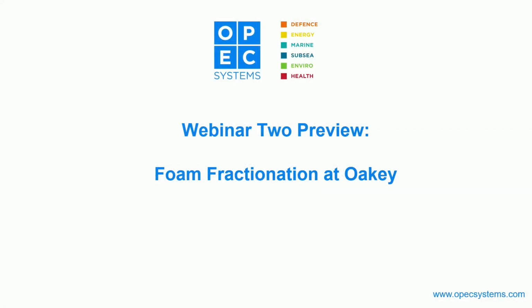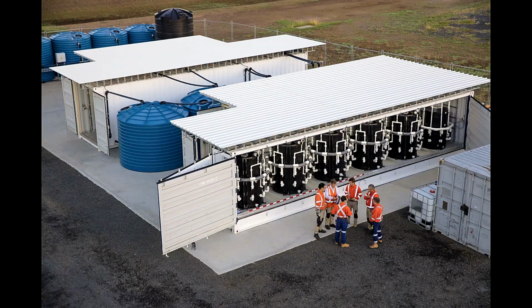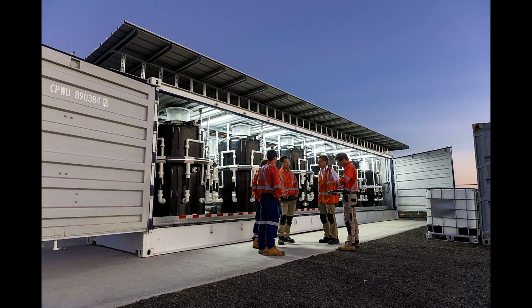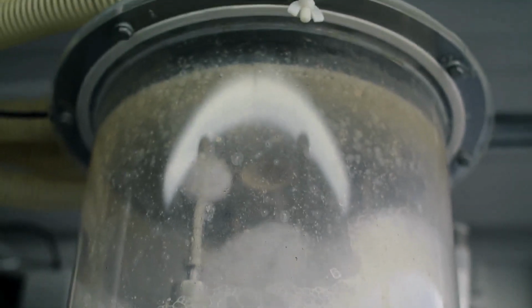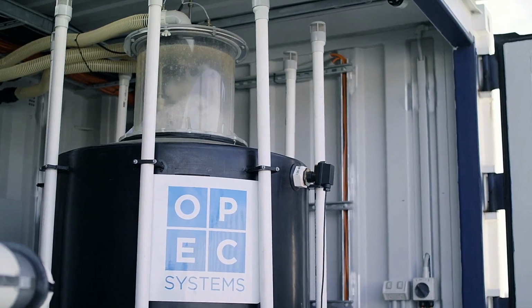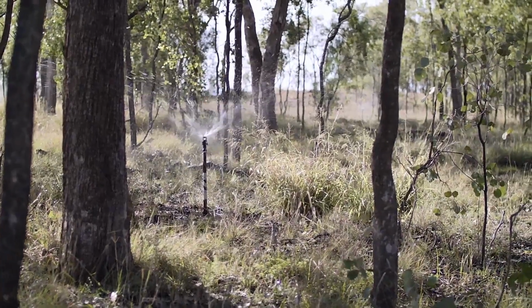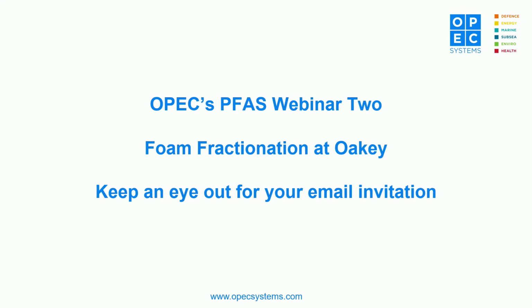I mean, the Oakey site's, I guess, our flagship at the moment. It's one of the largest systems we've built. So you can see at the front, you've got the fractionator columns there, some of the pre-treatment and resin systems behind it. But effectively, that's a 67,000 gallon per day system that's doing this fractionation. So this is PFAS coming out of groundwater in the field there, and we're treating that to drinking water standards for discharge to the environment. We're also using that treated water for re-injection into the aquifer. We've also partnered with a couple of the construction companies on site to provide water for dust suppression. So it's cleaned, it's ready to go back in the environment. Close the loop there.